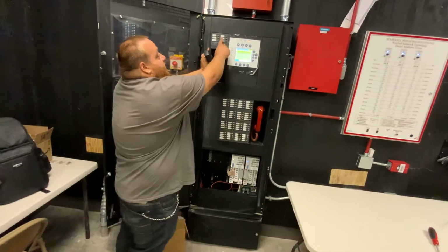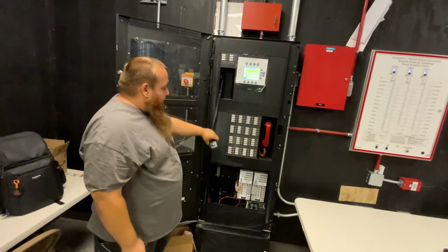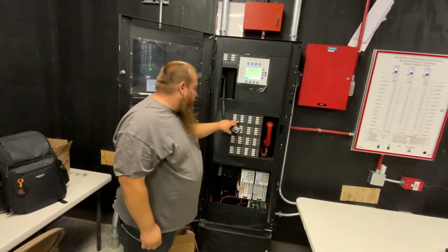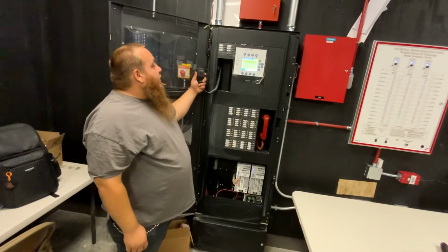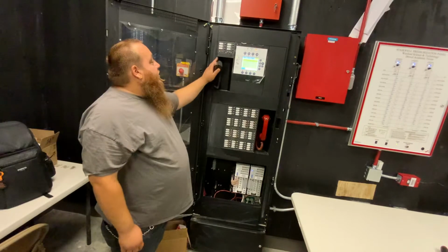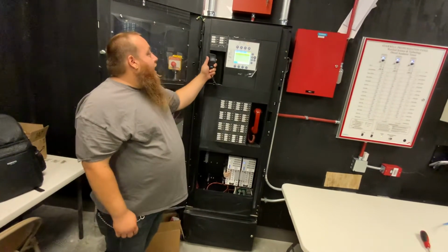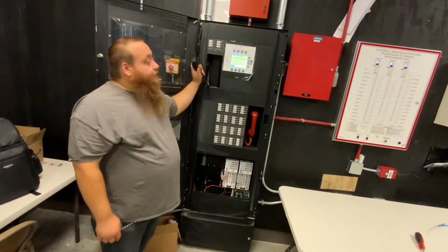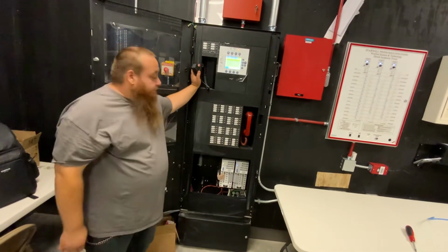Then you also have your selected page. You would select that button. You could even pick out a floor. You can just pick fourth floor, and then you cue your mic. You see how it has a pre-announce tone? Once it says ready to page, you'll be able to talk into your microphone. That won't happen unless you cue your mic. Once you're done, it turns right off.